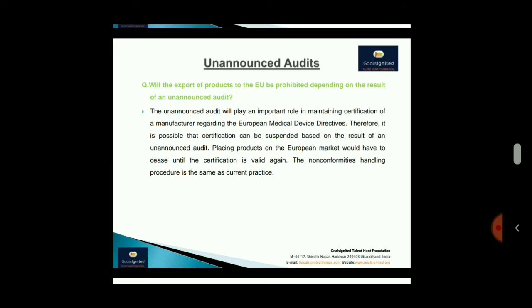The unannounced audit plays an important role in maintaining the certification of a manufacturer regarding the European Medical Devices Directives. Therefore, it is possible that the certification can be suspended based on the result of an unannounced audit, and placing products on the European market would cease until the certification is valid again. The non-conformity handling procedure is the same as the current practice. So you have to take the unannounced audit very seriously, because these are surprise checks, and the people who come to audit the site are quite knowledgeable, quite good in their findings, and they audit the site as investigators.